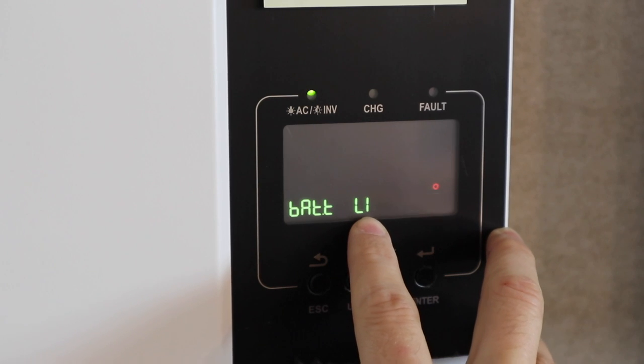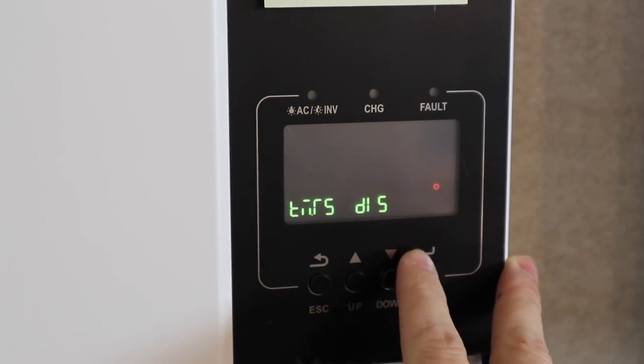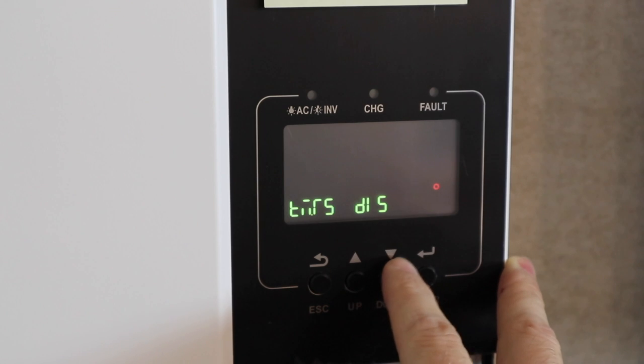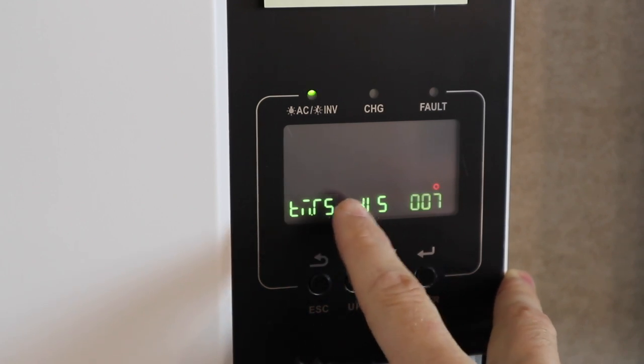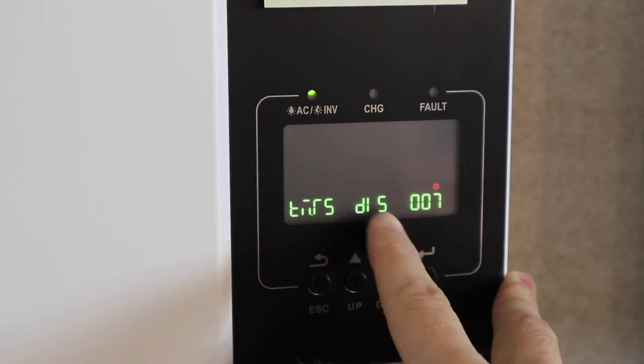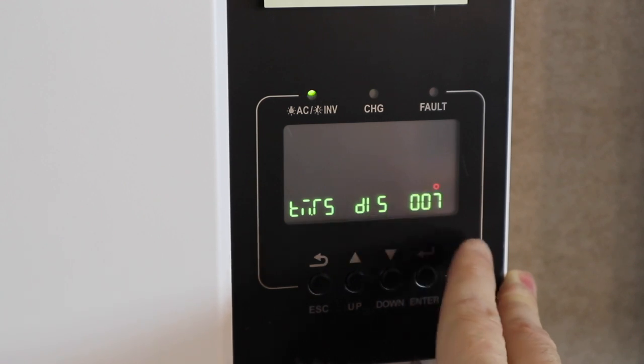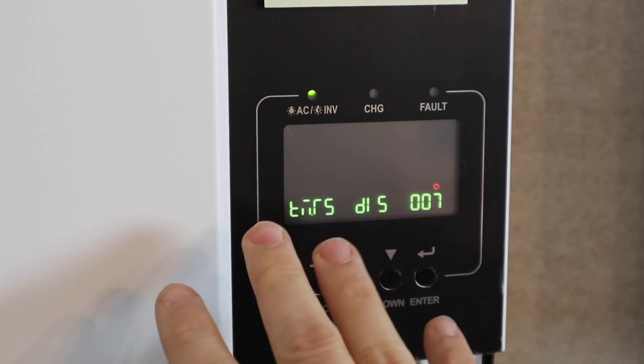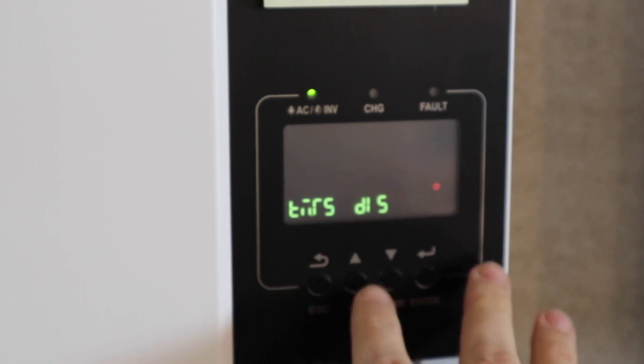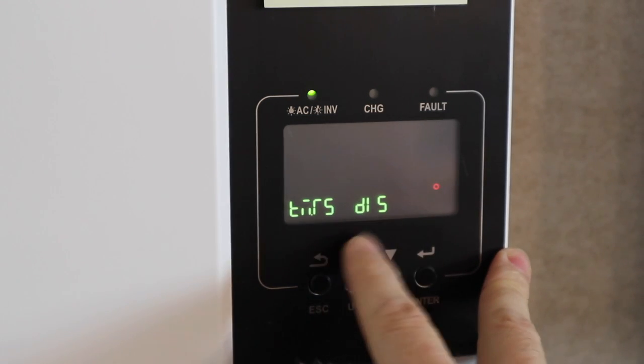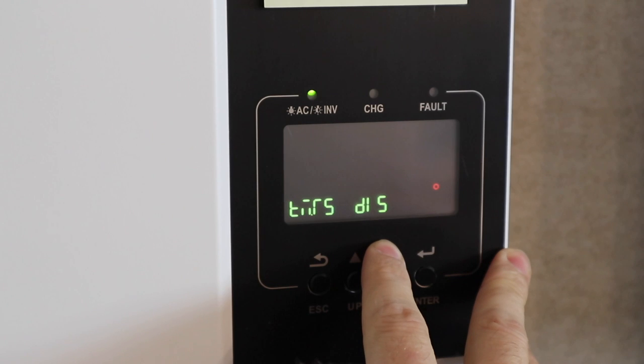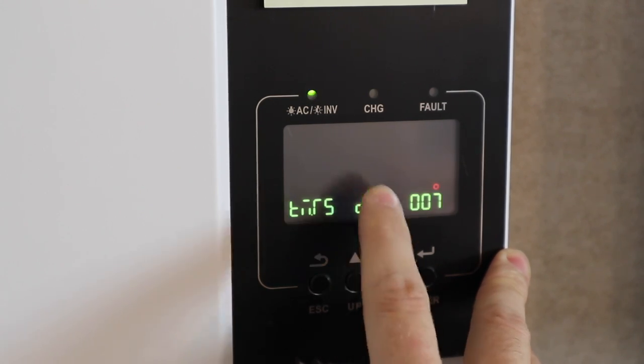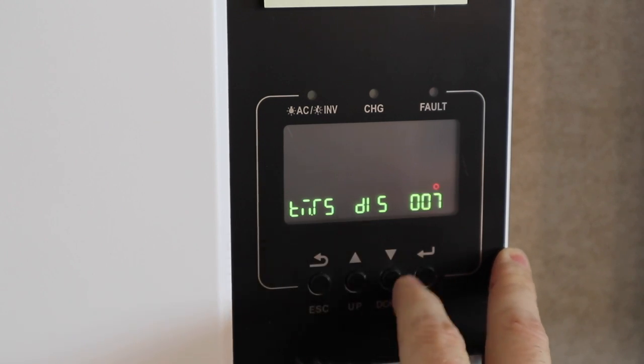If not, you have to set it at user 2. 6 and 7, we are gonna leave on the defaults. And that is just temperature settings for overloads and auto restarting. If we have any issues with overloads or anything with these inverters, I don't want them to auto restart or keep auto restarting. I want to figure out what the problem is before I damage the inverter. So no auto restarts for us.